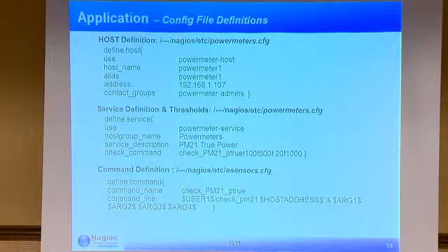You can use the command check PM21, and the 4 values which are given here, 100, 500, 20, and 1000, which you see here where I'm pointing. Those are the thresholds which are specified. You can change them based on your requirement. And this service is for the true power. Each parameter measured by a device is considered a separate service and listed under a host.